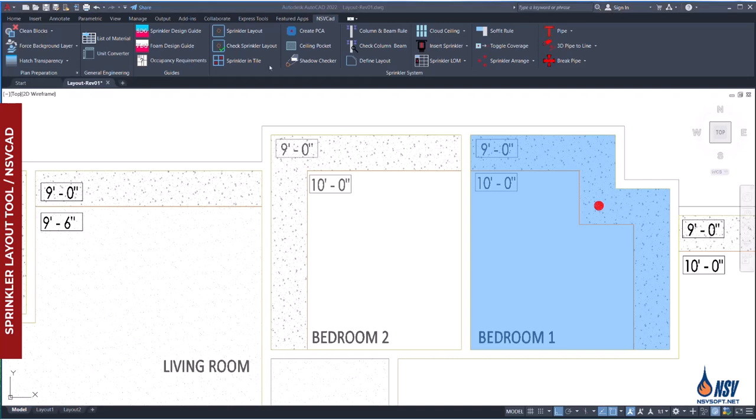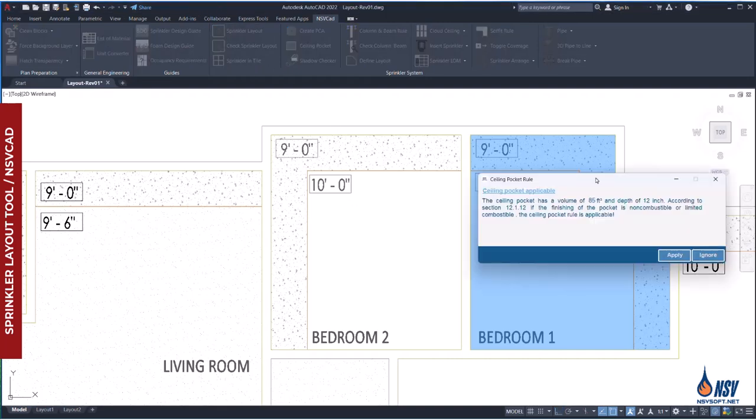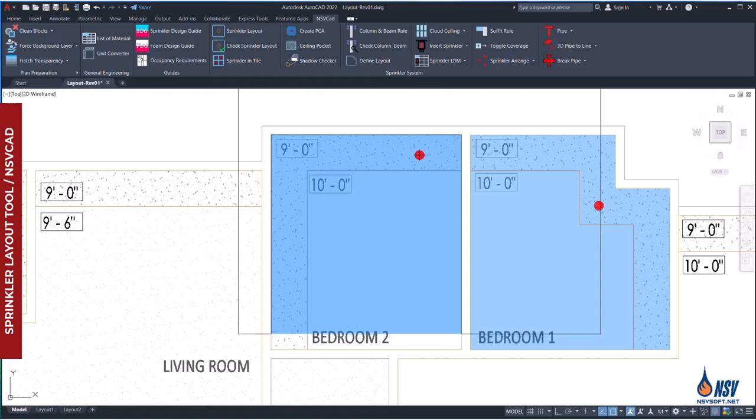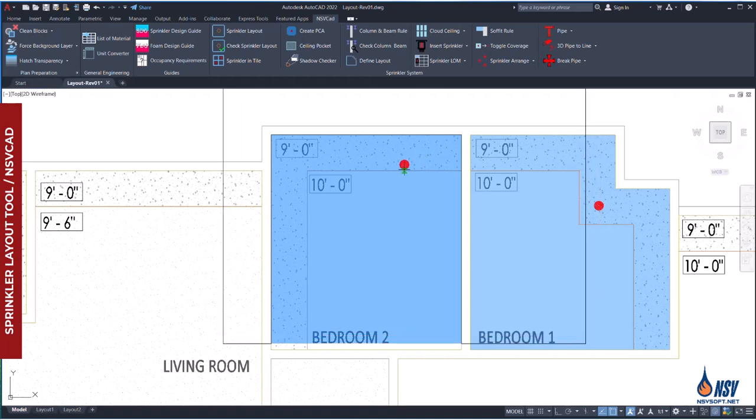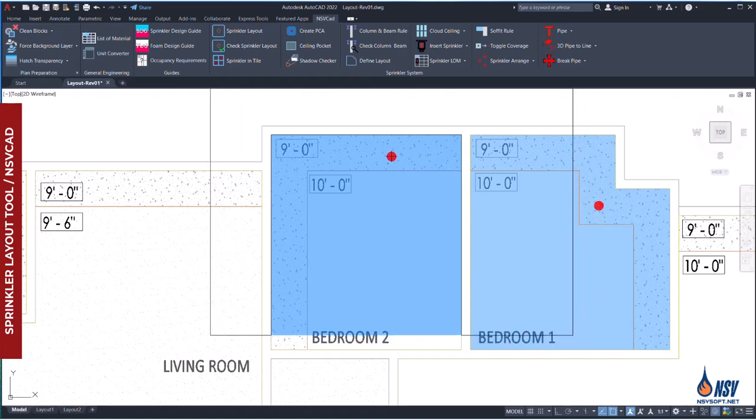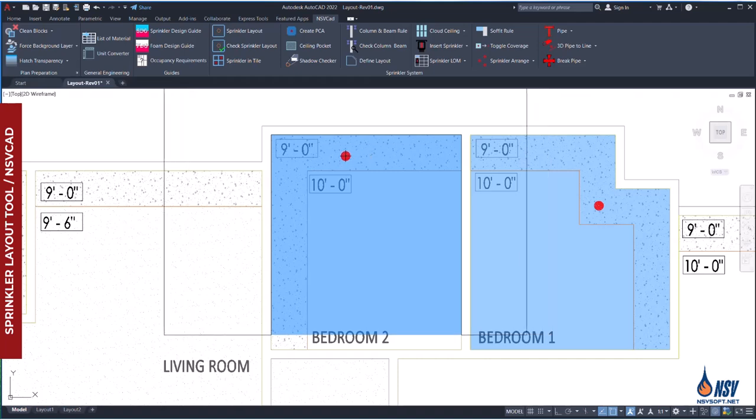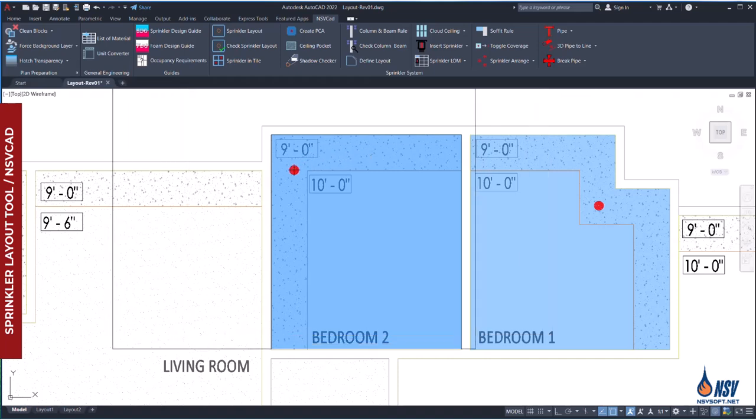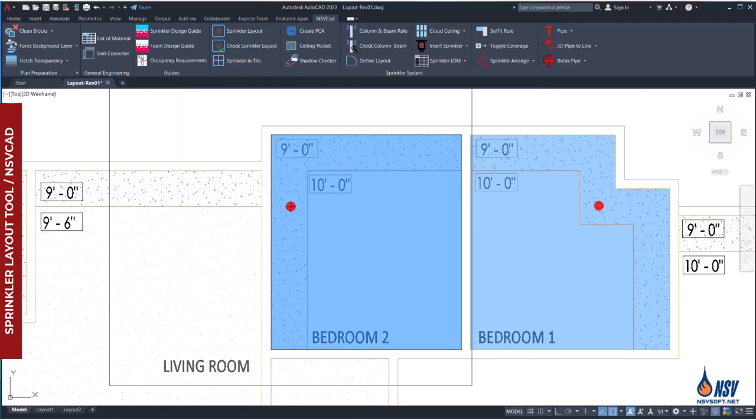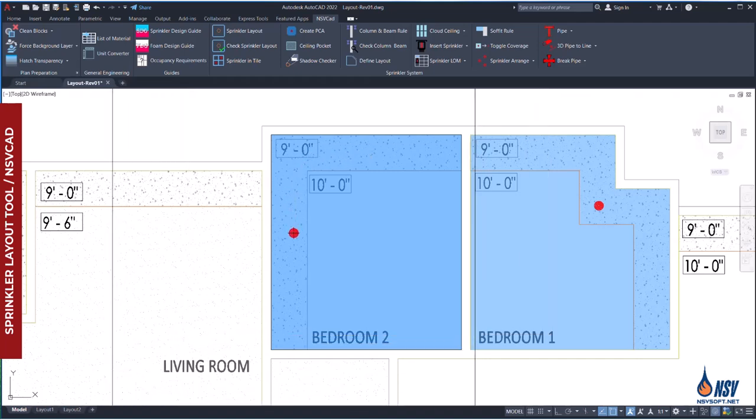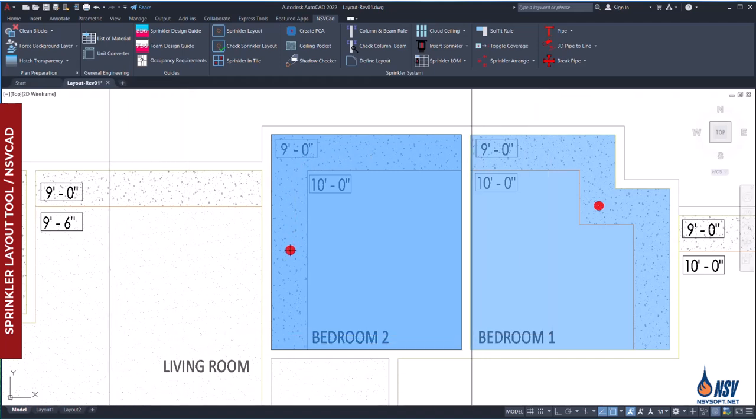Now, in bedroom 2, the ceiling pocket allowance is also applicable. If we place the pendant sprinkler under the north soffit, it fails to cover the southern portion of the room. However, by relocating the sprinkler beneath the west soffit, we achieve full coverage of the space with just one pendant sprinkler.